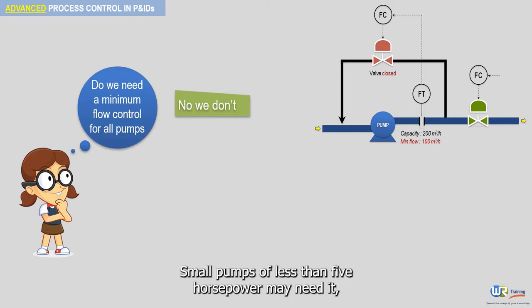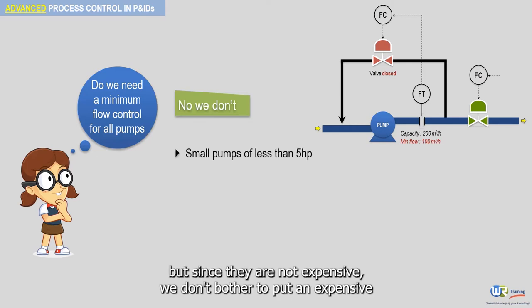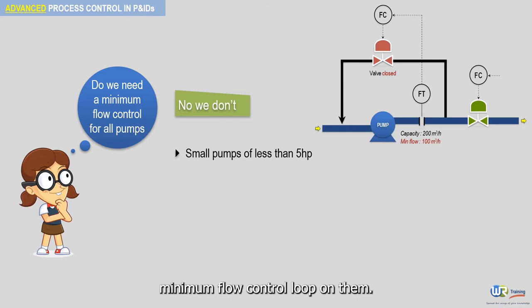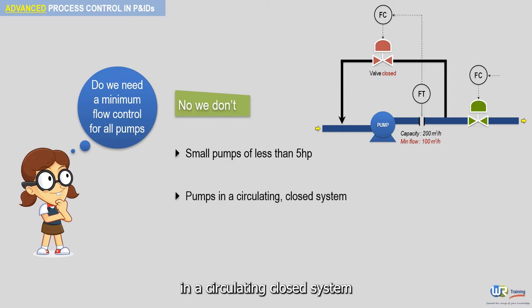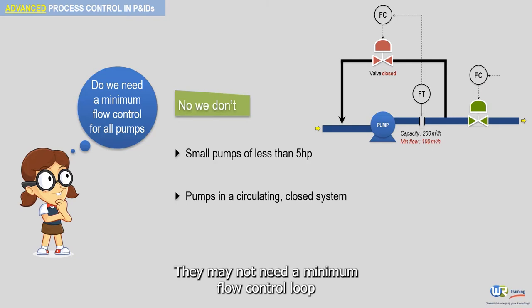Small pumps of less than 5 horsepower may need it, but since they are not expensive, we don't bother to put an expensive minimum flow control loop on them. Another example is pumps in a circulating closed system — they may not need a minimum flow control loop because the flow in such pumps is fairly constant.